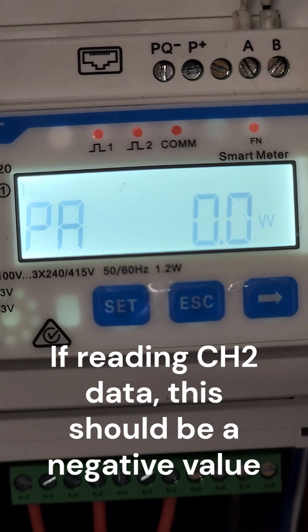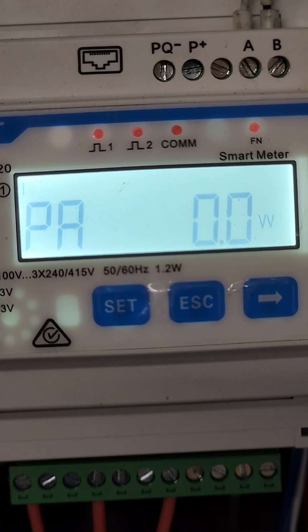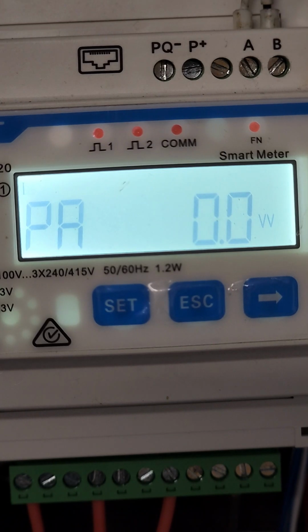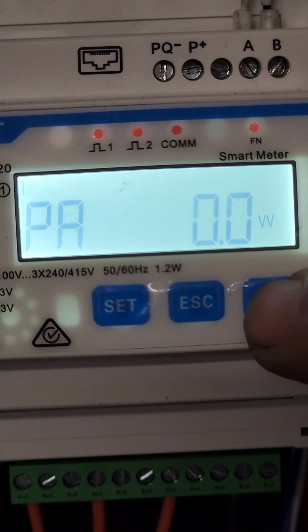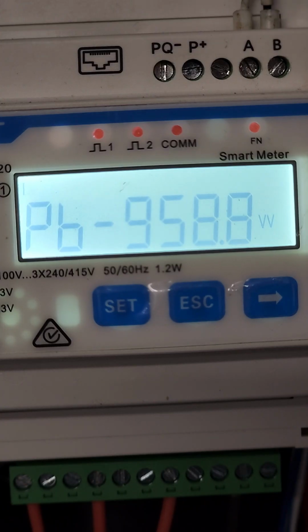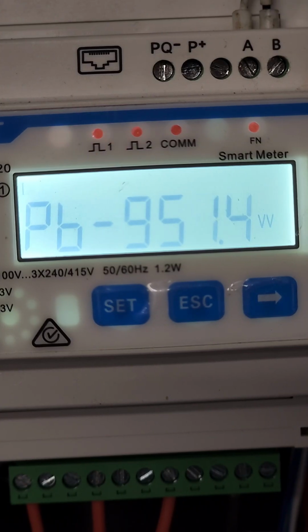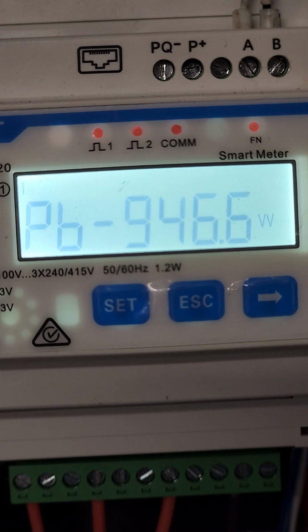However, if I move my load over to A phase, I've got a positive number. Move over onto B phase, I've got a negative. So my CT is reversed.